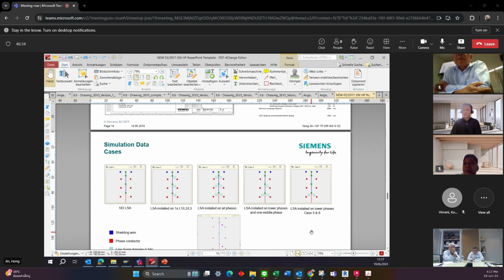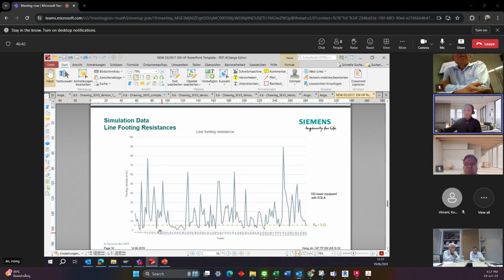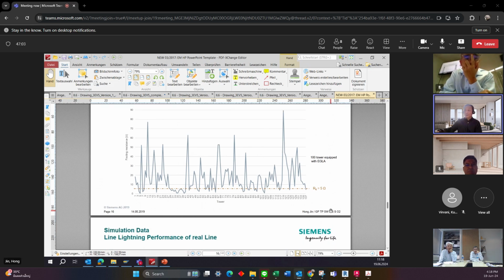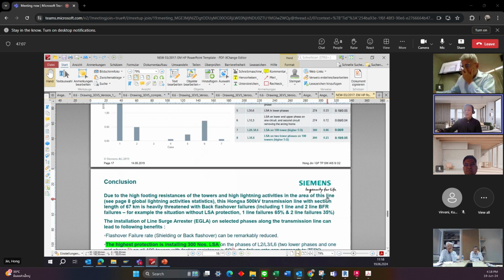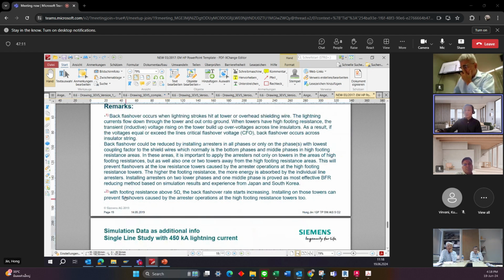So you need the final tower ground resistance, right? Yes. If you see, this is Hongsa. At that moment, we received the Hongsa footing resistance. So for some Hongsa towers, they have roughly 90 ohm. And for us, 5 ohm is a critical line, which means we can input all those footing resistances in the software. Thereafter, you will see the result from the last line study for Hongsa. With footing resistance above 5 ohm, the back flashover rate starts increasing. So basically, those towers must be installed with surge arrestors to avoid the flashover.